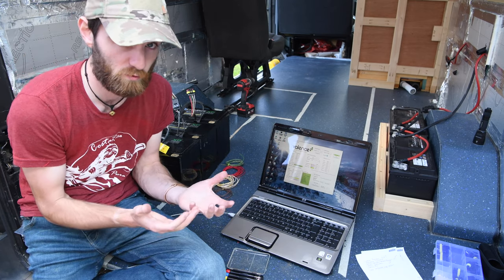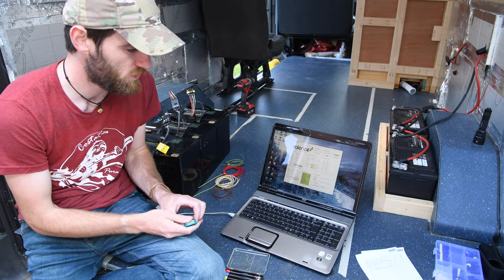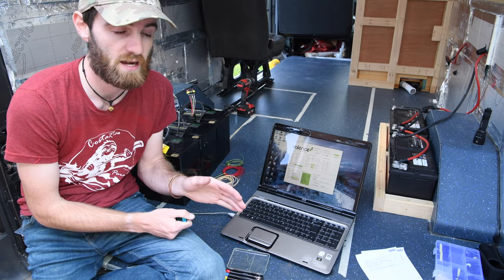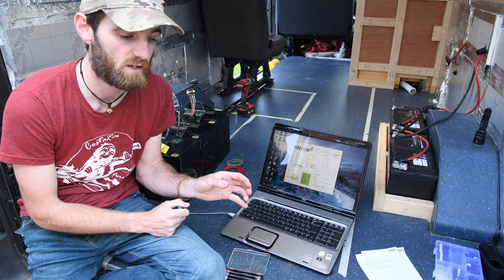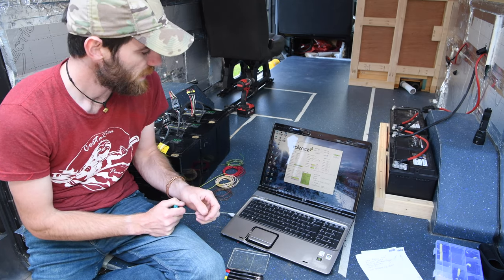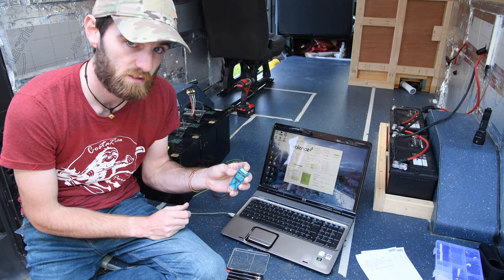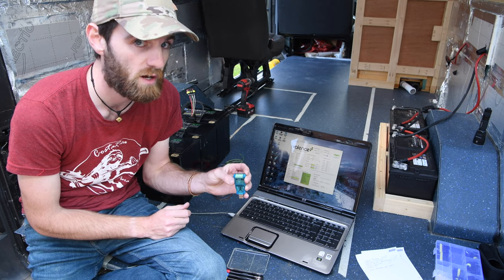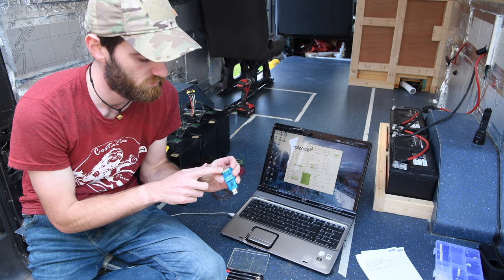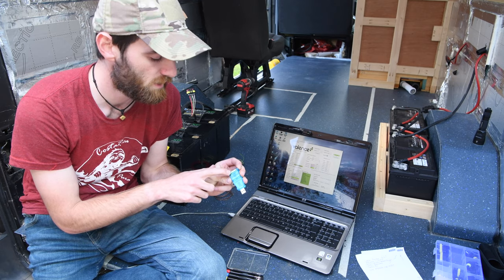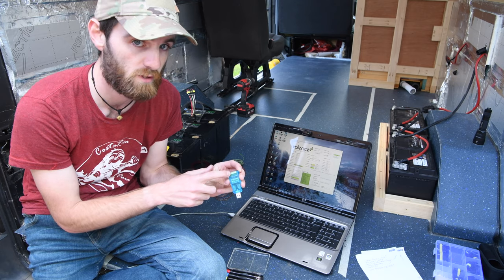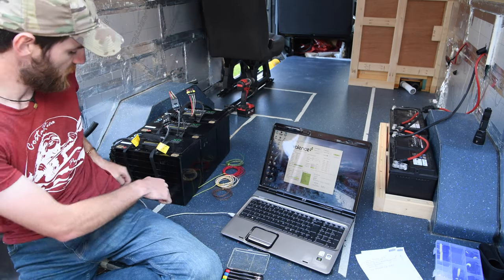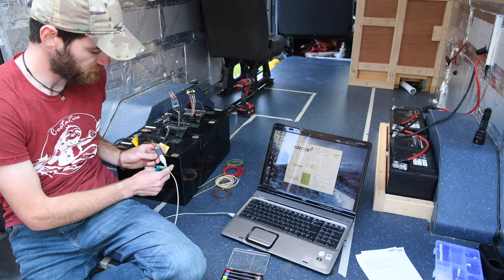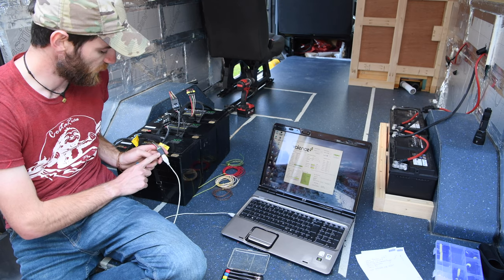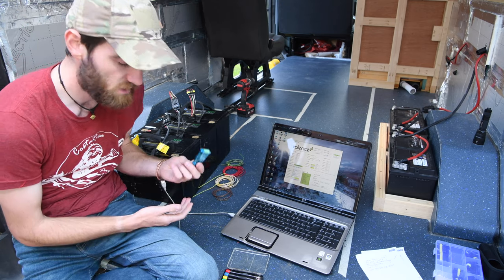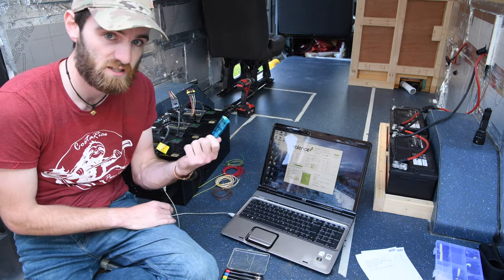So my actual problem was my communications cable. The instructions on the serial adapter to USB were a little bit vague and I didn't realise that the A and B plus and minuses had been swapped around. If you've got one of these ones instead, these blue ones off Amazon, I couldn't get this to work. I'm not saying it's not going to work, but I think the issue was it wasn't supplying 5 volts. They were supplying 4.17 volts through its positive cable. And I understand that these need 5. On my black adapter, again, this was supplying 5 volts, and after I got the cables right, it worked first time. But these were only cheap off Amazon. These were probably about, I think, £8 and £13.